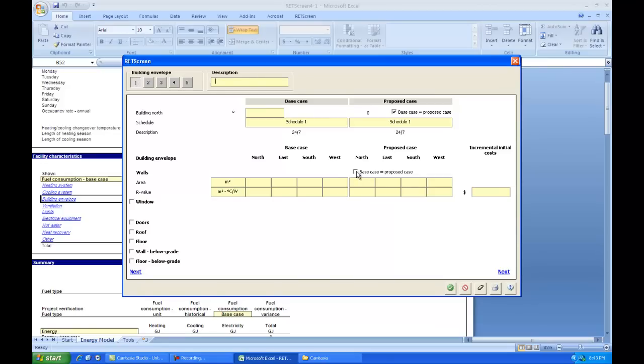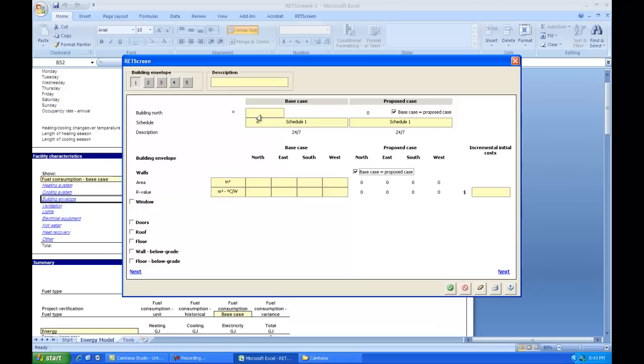I'm going to click base case equals proposed case for most of my work here. So this is the area of the wall. This is the direction that it faces. And this is the R value of the wall. Up here we have building north. Building north is the number of degrees that the wall that we're calling the north wall probably won't face exactly north. So if it faces 10 degrees to the east of north or 10 degrees to the west of north or whatever it is, that's where we enter it here.